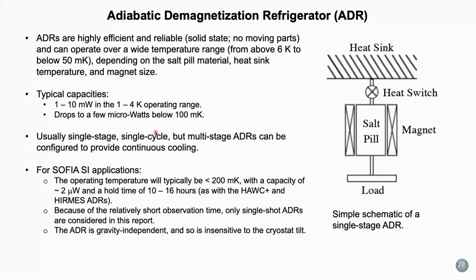Typical cooling capacities are 1 to 10 milliwatts in the 1 to 4 Kelvin operating range. That drops dramatically down to a few microwatts below 100 millikelvin, as I've said a few times so far. Usually there's single stage, single cycle, but multi-stage ADRs can be configured to provide continuous cooling.